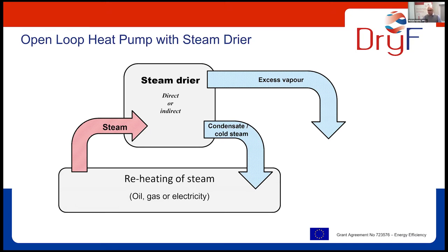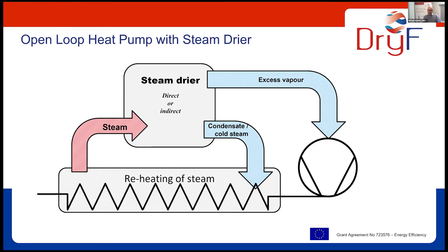in order to get again hot steam, which can be used as an energy supply for the steam dryer. So what we have been doing in the DryFiciency is that we took this very nice excess vapor, which was almost 100% pure vapor at one bar, and we compressed it up to a higher temperature and pressure level so that we can use this excess vapor now to reheat again the steam, as illustrated here in a simple heat exchanger.